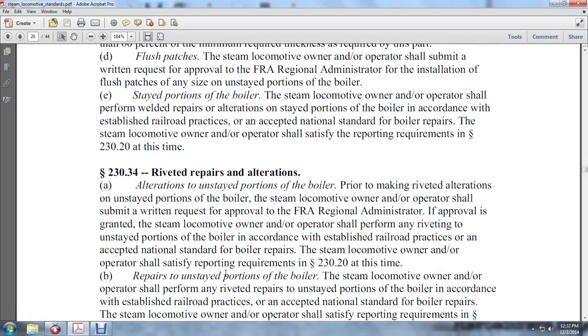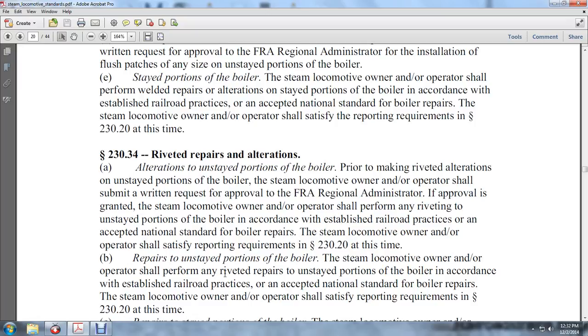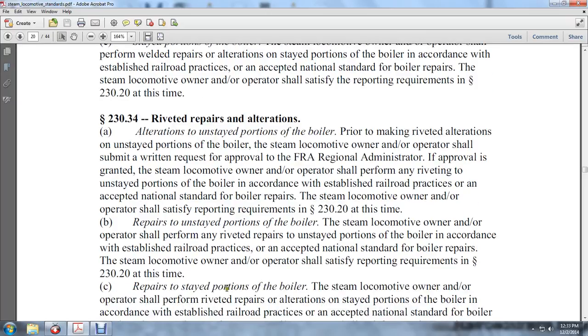Section 230.34 — Riveted repairs and alterations: For making riveted alterations on unstayed portions of the boiler, the steam locomotive owner and operator shall submit a written request for approval to the FRA regional administrator. If approval is granted, the steam locomotive owner and operator shall perform any riveting to unstayed portions of the boiler in accordance with established railroad practices and accepted national standards for boiler repairs, and shall satisfy the reporting requirements of 230.20.